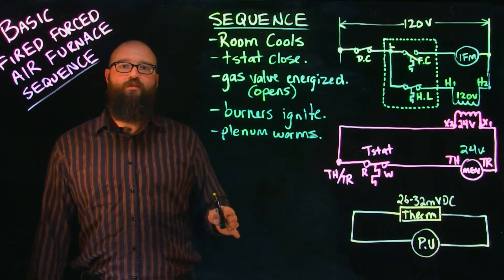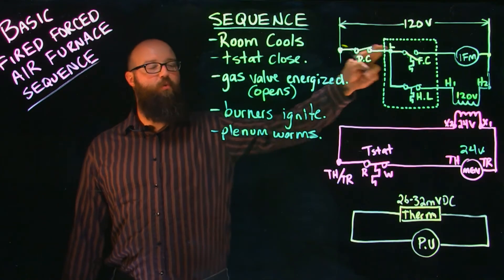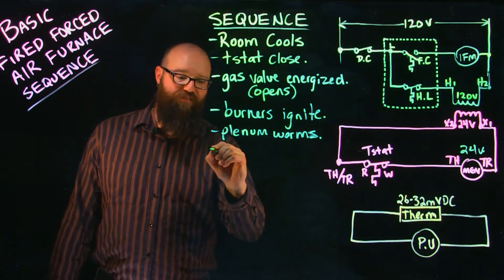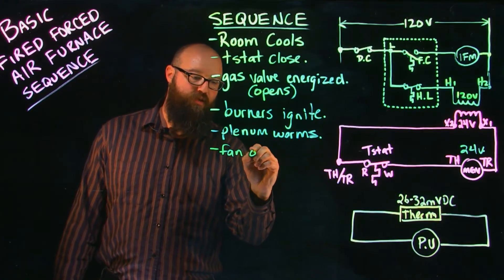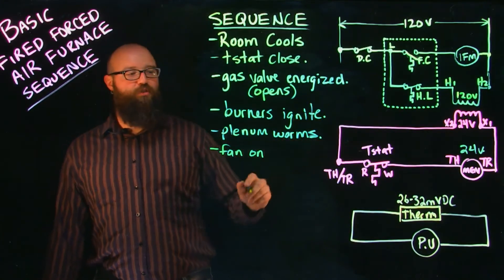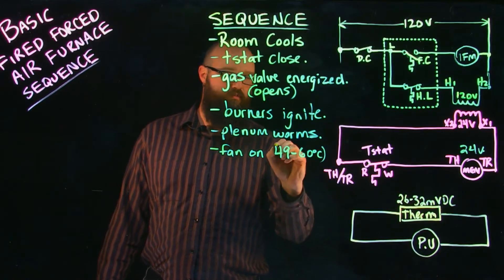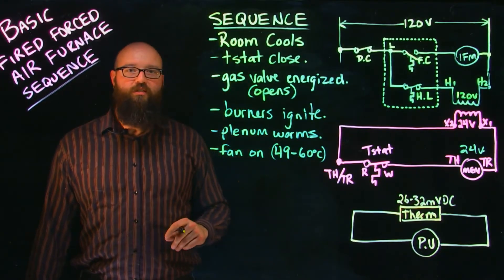As the plenum warms it starts to reach what we call our fan on temperature on our fan control. Fan on. That temperature is usually somewhere from 49 to 60 degrees Celsius.